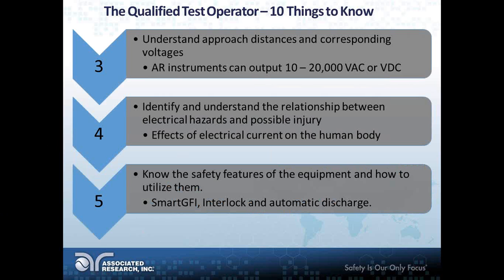The approach distance for an unqualified operator is 10 feet. That's a newer OSHA requirement as well, which I know OSHA bases their stuff off of the NFPA and NEC. But if you are not a qualified operator working in or near a dielectric withstand or hipot testing station and the circuit is active and you have exposed conductors, they're not to get within 10 feet of those exposed conductors, and that's an important number to remember. If an auditor were to come through and see you getting closer than that to such a circuit, you can be fined for every single instance of somebody getting within that. So not just one guy happens to make a mistake.